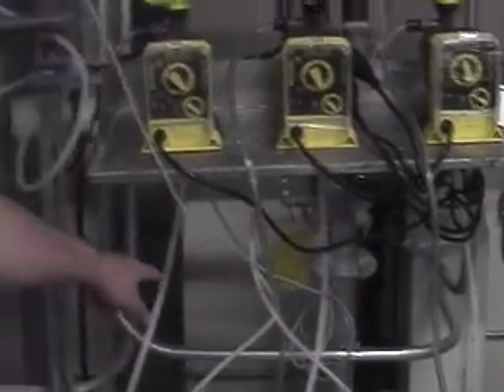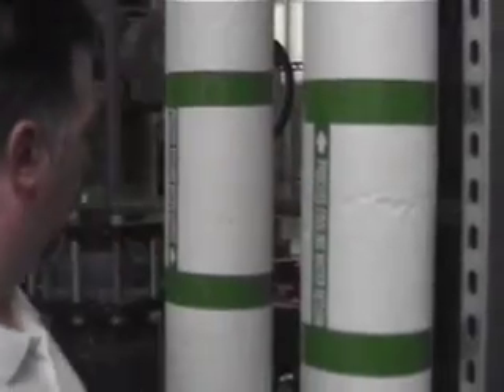Then you've got your solid separator right here. There's a blowdown valve for that located right behind it. So this is the valve I was talking about that we open once a day if the condenser water flows have run at all during that day. And it just opens for like 30 seconds.